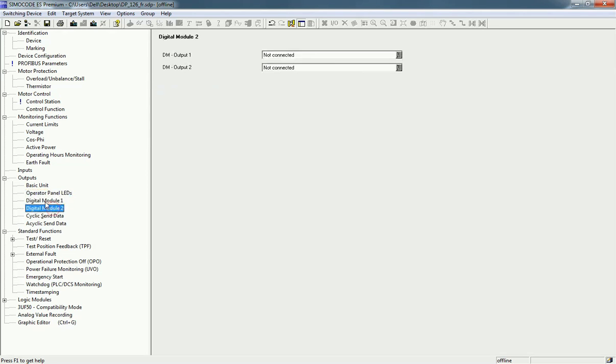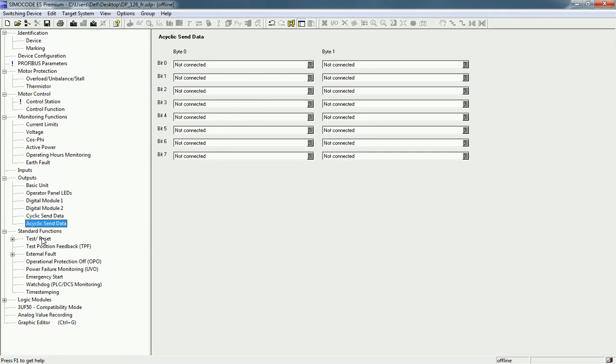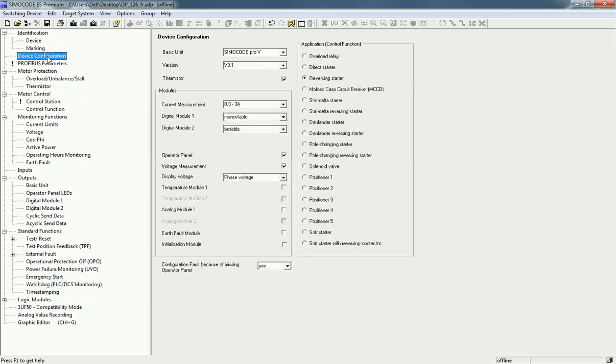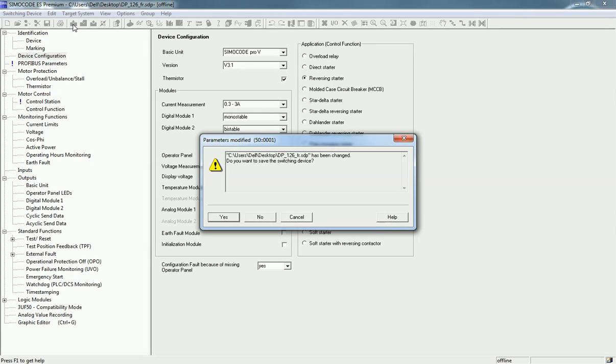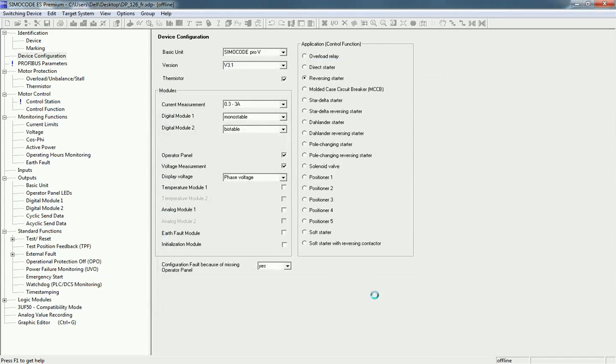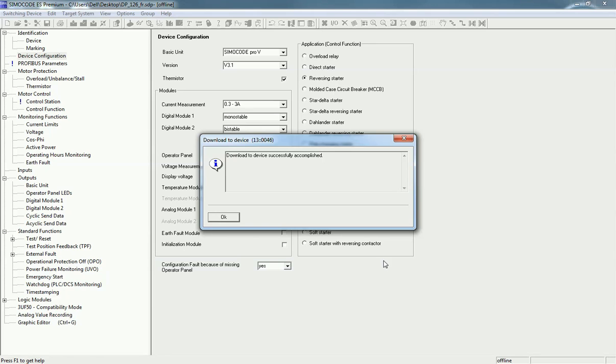The digital module, cyclic send data, test, and reset are additional options available in SIMOCODE that we will see step by step in every video. After configuring the device, click on 'Load All Parameters to Switching Devices.' I have connected a USB cable with the kit, so I click the button, select the COM port to which the USB cable is connected, and click OK. After configuring the device, you will get the message 'Download to device successfully accomplished,' which I will then acknowledge.